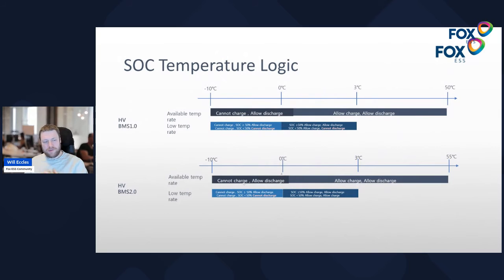So the state of charge temperature logic, this is a slide from Fox, and it's really interesting to see there are a couple of differences that I wasn't aware of until I really paid attention to this slide. That's the difference between a version 1 BMS and a version 2. The only difference I can see is that a version 1 won't allow you to discharge below 3 degrees if the state of charge is under 50%, whereas on the version 2 it's fine. It's allow discharge, allow charge for everything right up until you get to negative Celsius.